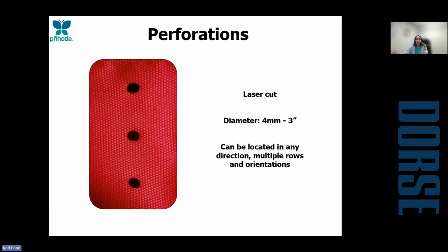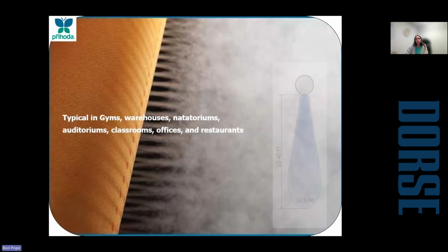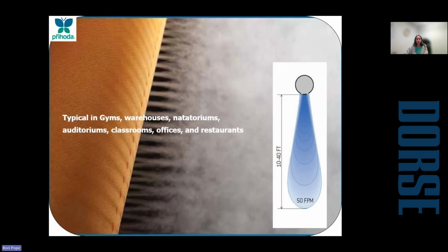The most common air distribution method that we use is perforations. These again are laser cut holes that can be located at any orientation on the duct with as many or as few rows as are needed. These come from 4 millimeters up to 3 inches in diameter. And these are typically what's going to be used for your gyms or smaller warehouses. These can throw upwards of 40 feet.